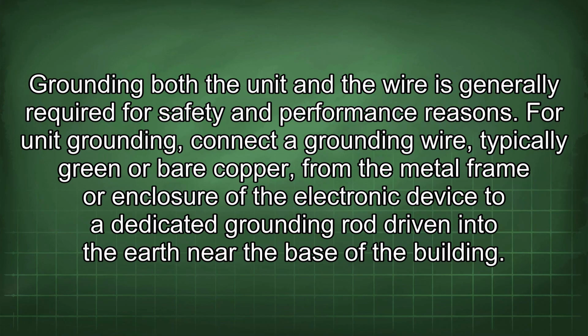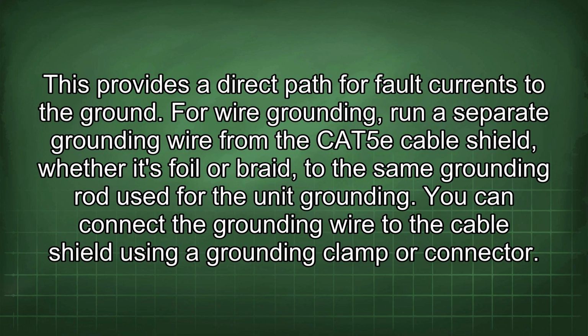Grounding both the unit and the wire is generally required for safety and performance reasons. For unit grounding, connect a grounding wire, typically green or bare copper, from the metal frame or enclosure of the electronic device to a dedicated grounding rod driven into the earth near the base of the building. This provides a direct path for fault currents to the ground.